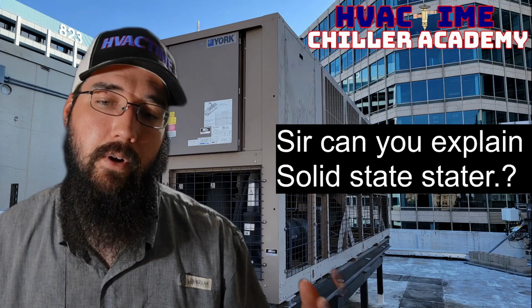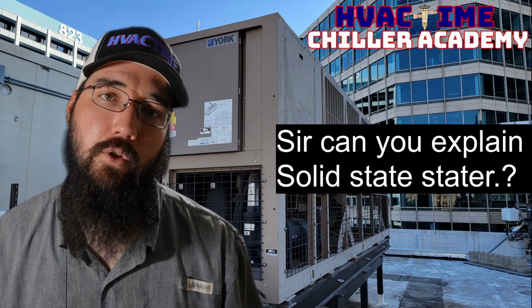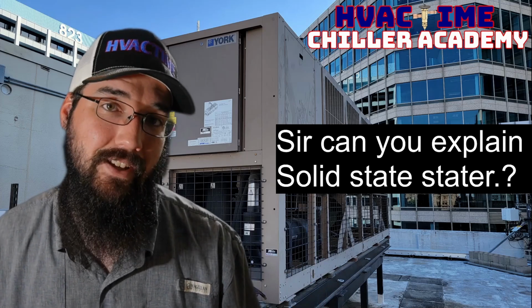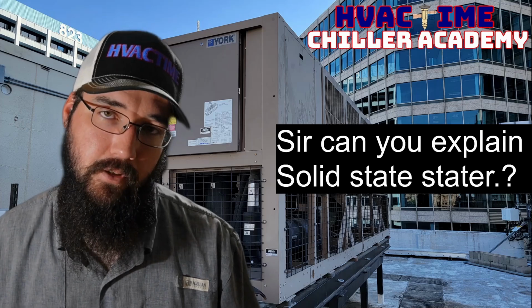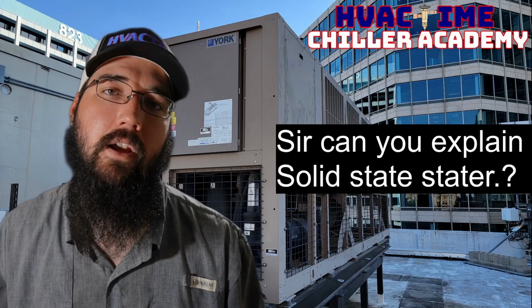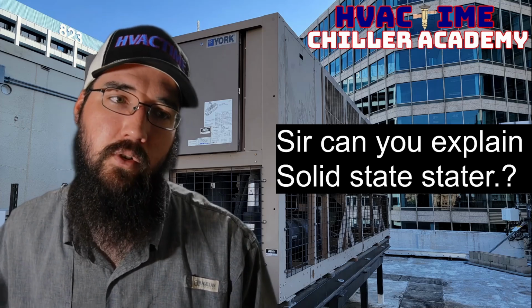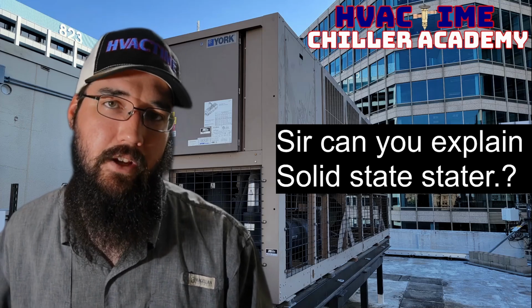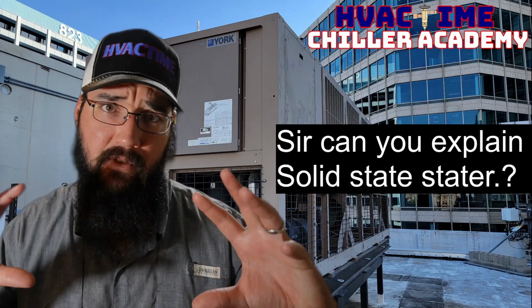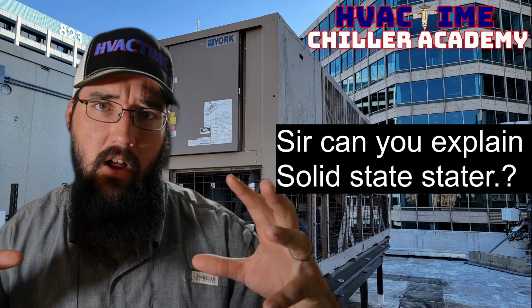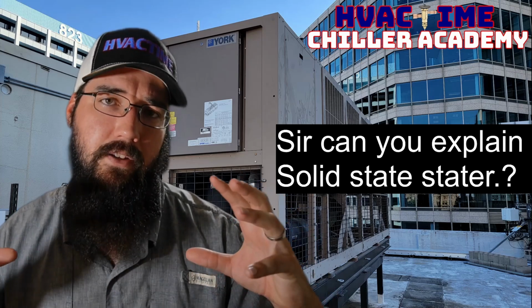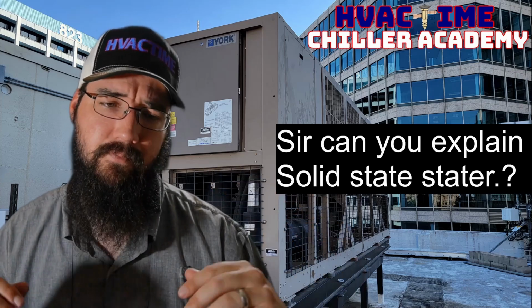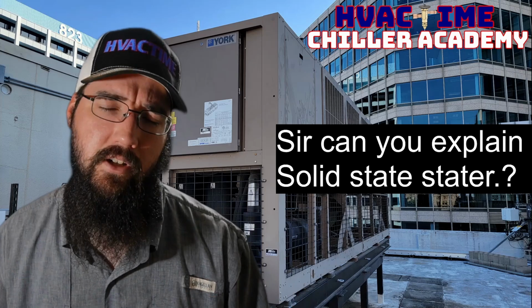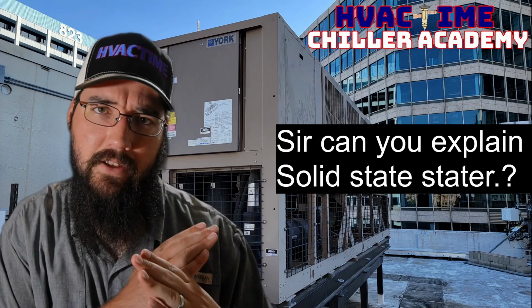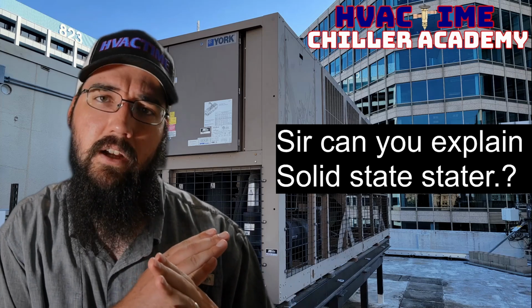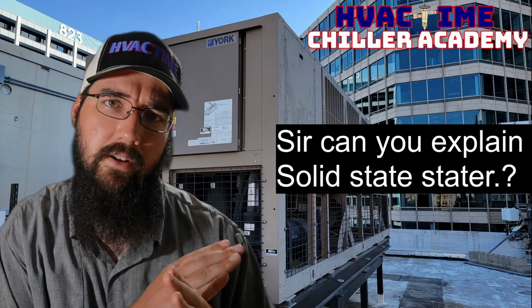contactor in a regular split system, an RTU that just closes, compressor turns on, that is an XL starter. It's just a small contactor. And that is true once we scale into a much larger application where we may have a genuine large starter block, but it's just one of them that is an XL start. And XL is literally referring to across the line. So X is cross on electrical schematic. That's what that is referencing.